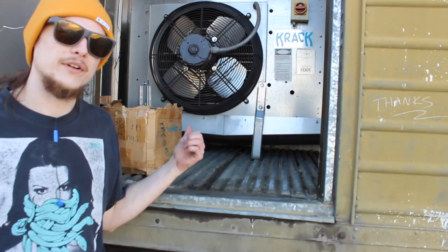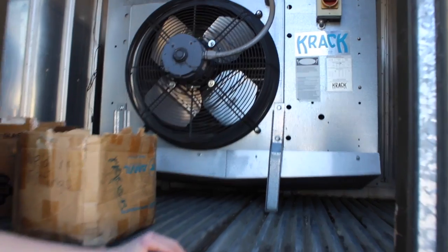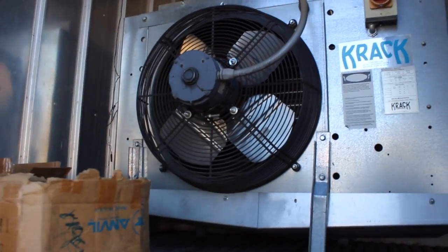This system has two evaporators. This is one of them. It's an induced draft, and they are flooded evaporators, meaning most of the coil is filled with liquid.